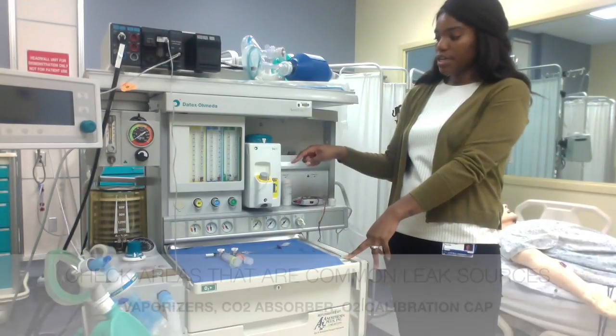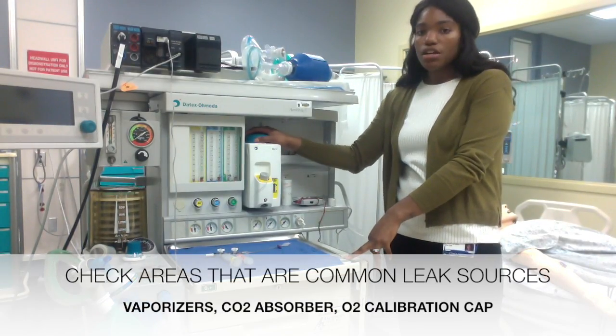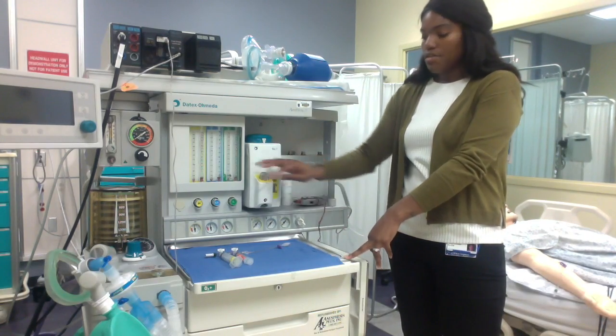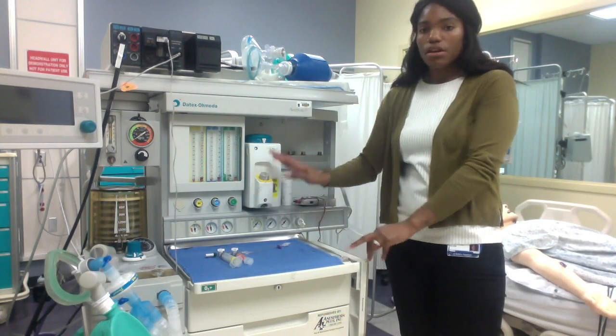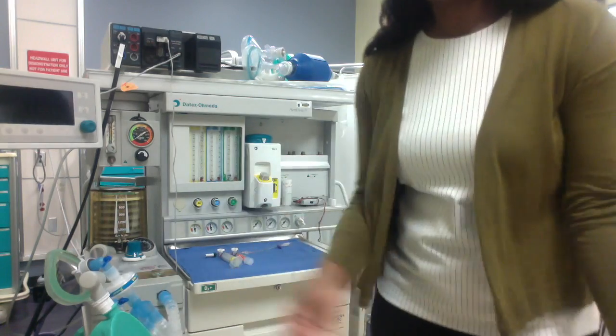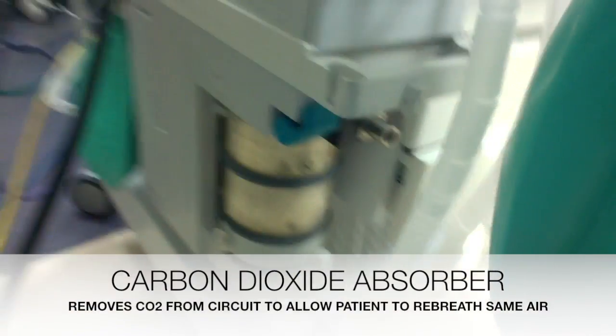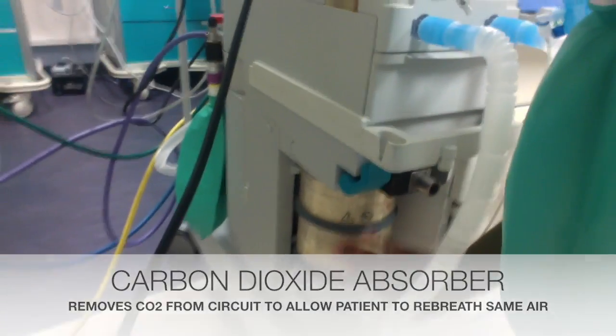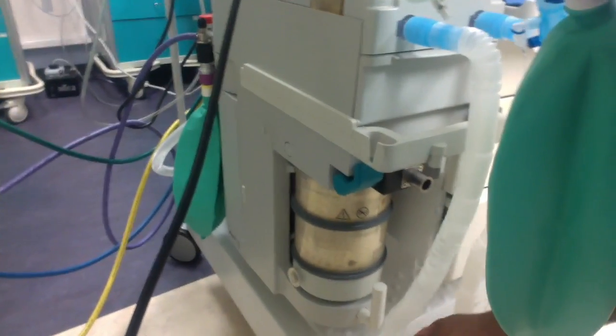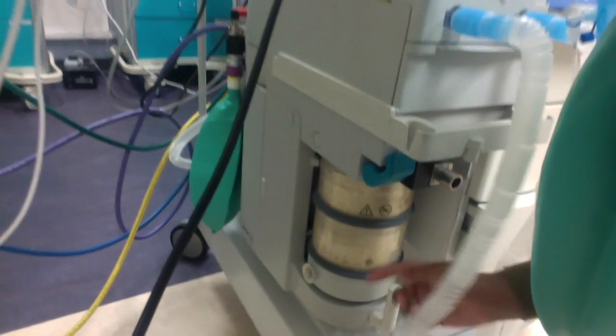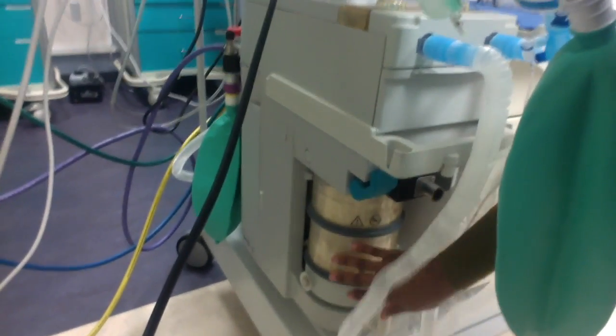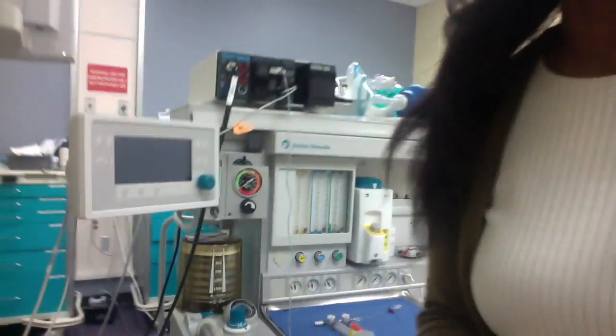And so the first thing I would do is I'd make sure that my vaporizers are nice and secure. They're seated properly, they're filled, and the caps are nice and secure. I would also come down here to what is called a CO2 absorber, and that scrubs all the CO2. It takes the CO2 out of the circuit and allows the patient to breathe more fresh gas. And so I'd make sure that those are the appropriate color and that they're seated as well, because those are two common sources of leaks.